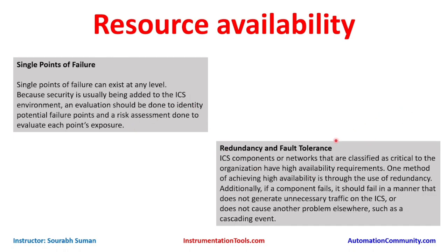For redundancy and fault tolerance, once all single point failures are identified, ICS components or networks classified as critical to the organization have high availability requirements. One method of achieving high availability is through the use of redundancy. For example, if a server is critical and has only one power supply, add a second power supply or a power switch with two sources that can converge to a single supply, or add an additional power supply if it is a modular server.